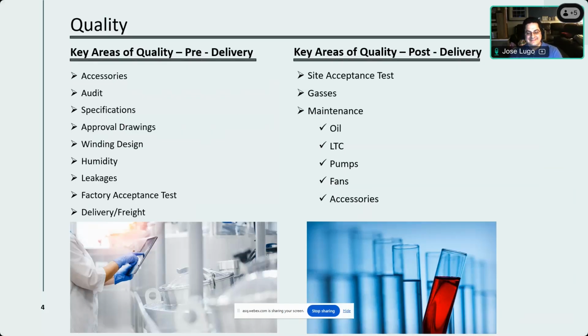Factory acceptance tests, which means you have to, well, you don't have to, right? But the quality of life is that you should witness personally the testing that they do on this device to make sure that everything passes per code, per standards. IEEE is definitely one of the big ones that most people follow, but you yourself can make it a little bit more stringent than IEEE. IEEE is a guide for industry-wide, but if you make it stringent, you can definitely push the quality of the power transformer at that point. And then there's delivery and freight, as I mentioned.